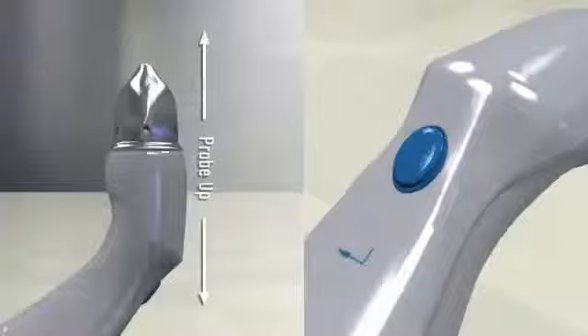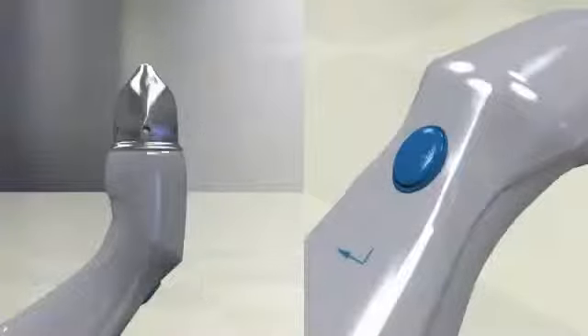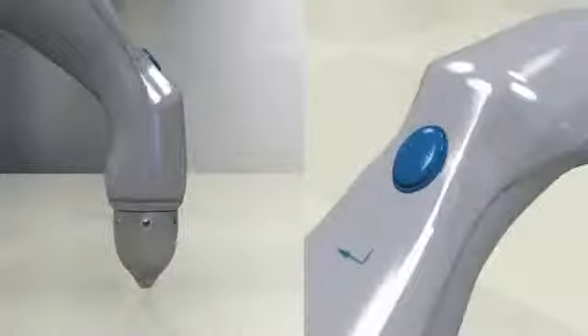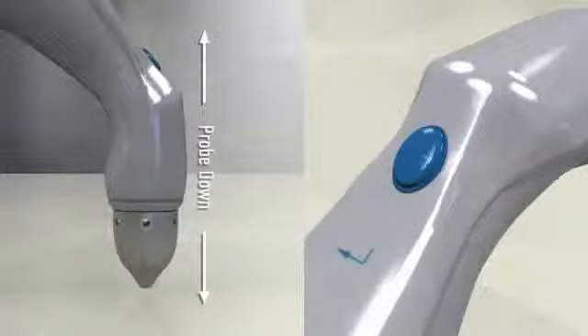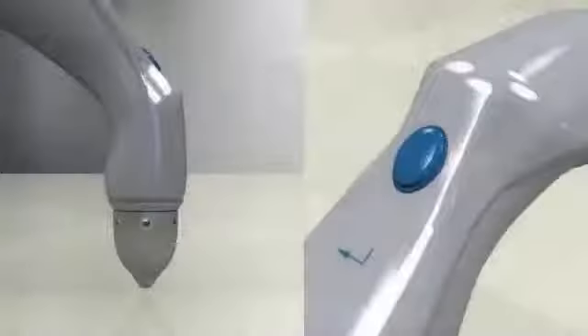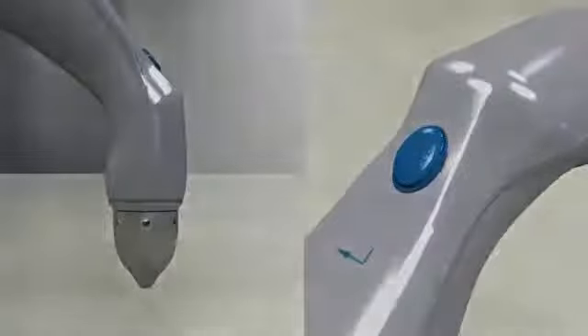The last step in the calibration requires the user to hold the unit so that the transducer is pointed directly towards the floor. Press the Action button. A calibration number will display on your AccuPen. Consult your user manual to confirm this number is within 30 of the engineered calibration number. When calibration is complete, the unit will feature a number under the probe.